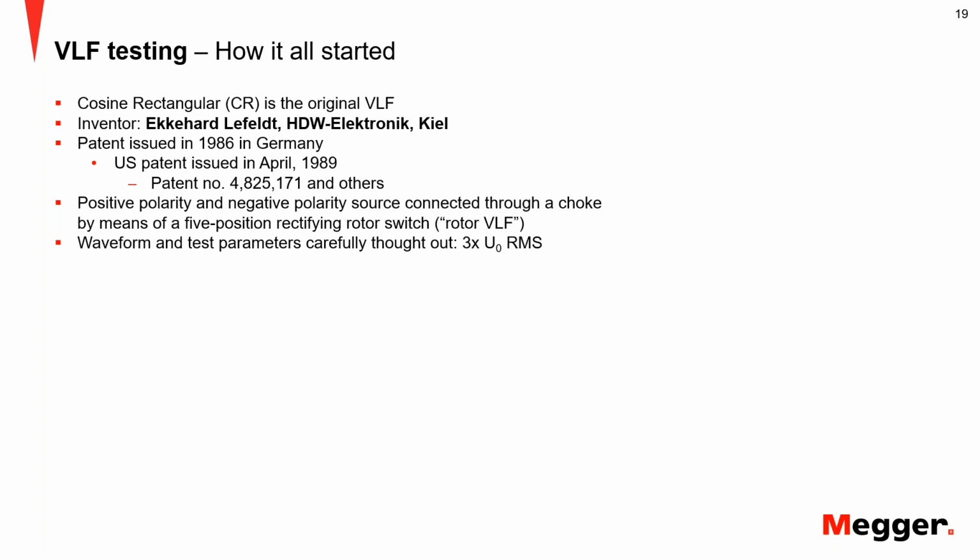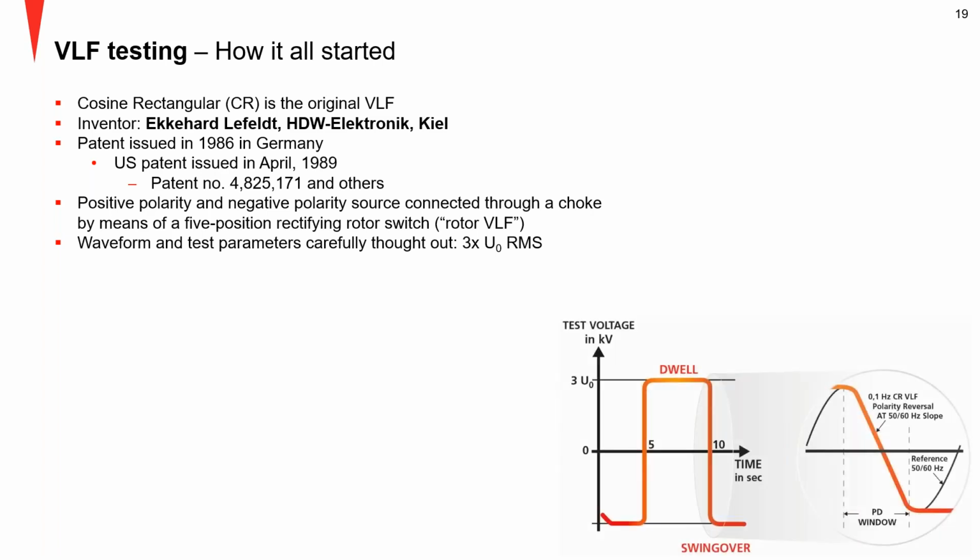And he came up with this idea: I have to build a test set with a certain waveform that has to be designed to have a field test equipment that is replacing the DC test, is an AC hipot in contrast, and achieves all these nice things: small, compact, lightweight, powerful, and duplicating as much from the AC testing as possible. And the waveform he pretty much came up with looks like this.